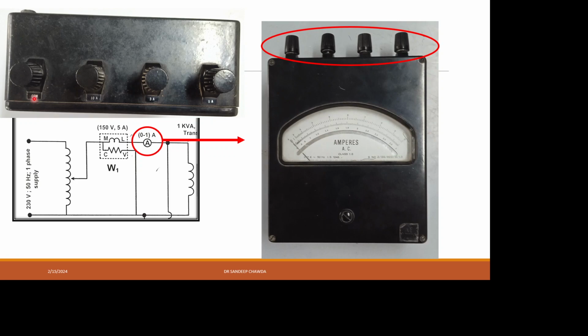At one end it is written common, and then 10, 3 and 1 ampere. This means it is a multi-range AC ammeter, which could be used for measuring current from 1 ampere up to 10 ampere. Different ranges are there. We require a 0 to 1 ampere range, so we have to utilize the common terminal and the 1 ampere terminal.